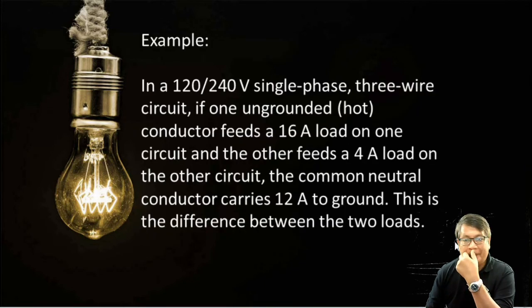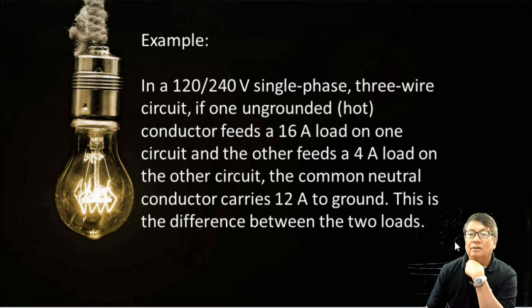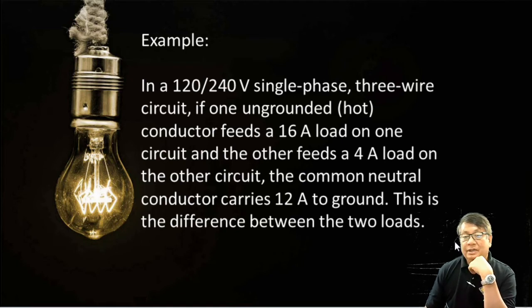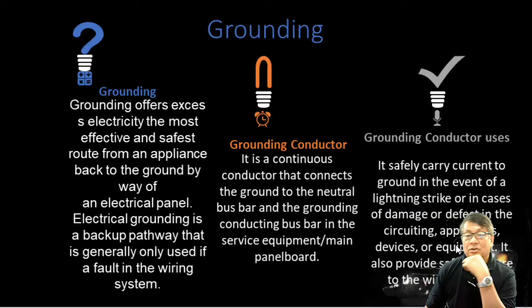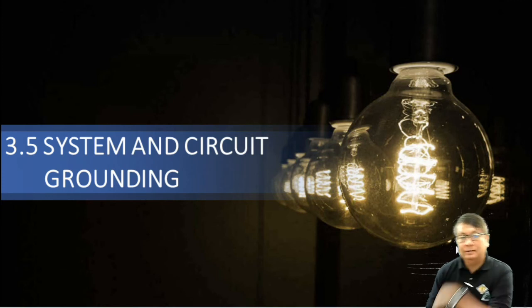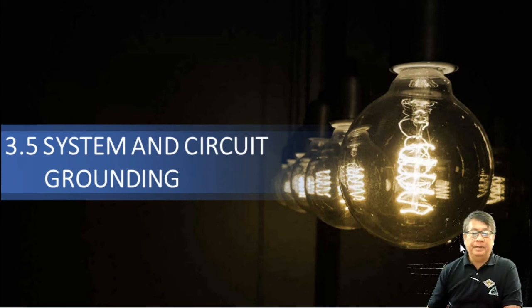Okay? So we have this in a 120/240 single phase 3-wire conductor. If one ungrounded conductor feeds a 16 ampere load on one circuit and the other feeds a 4 ampere load on the other circuit, the common neutral conductor carries 12 amperes to ground. This is the difference between the two loads. Okay? So, yan po. Number 3.5, we have this system and circuit grounding.